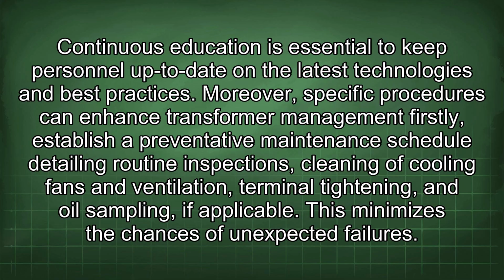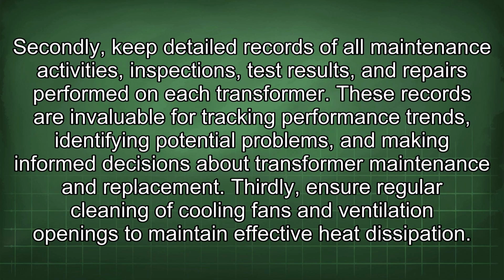Moreover, specific procedures can enhance transformer management. Firstly, establish a preventative maintenance schedule detailing routine inspections, cleaning of cooling fans and ventilation, terminal tightening, and oil sampling, if applicable. This minimizes the chances of unexpected failures. Secondly, keep detailed records of all maintenance activities, inspections, test results, and repairs performed on each transformer. These records are invaluable for tracking performance trends, identifying potential problems, and making informed decisions about transformer maintenance and replacement.